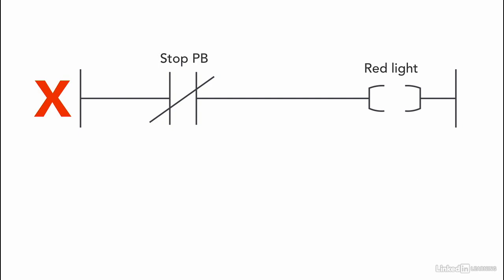The reason to use the conveyor memory bit address, and not the stop pushbutton, is that we need the light to be linked to the conveyor. Because if we use the stop pushbutton, then the red light will be on as soon as the stop pushbutton is pressed, regardless if the conveyor is on or off.